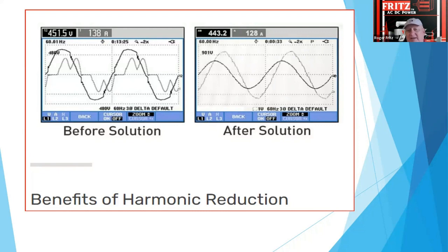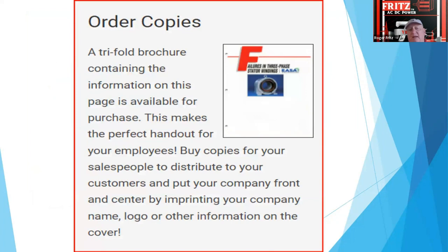So we actually work with a company that has a lot of patents on that technology, but they actually do feedback to compensate for this, and it's automatically resonating. And again, on the 20th, Heidi said we're going to give more in-depth detail of how those active front end filtering networks work. It's kind of a wave of the future that's happening because power quality is so important. And even the uninterruptible power supplies, a lot of people don't realize they're actually just a VFD with a fixed input and output frequency. And so they'll put off some noise factor, and we've run into that in some buildings.